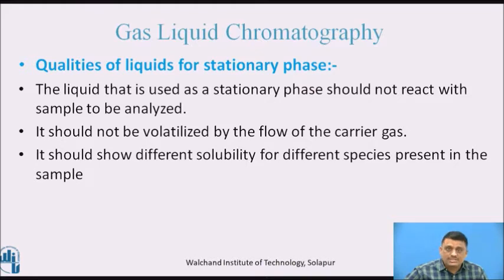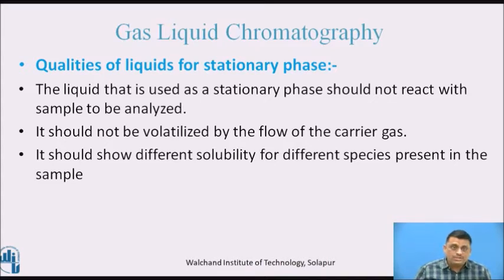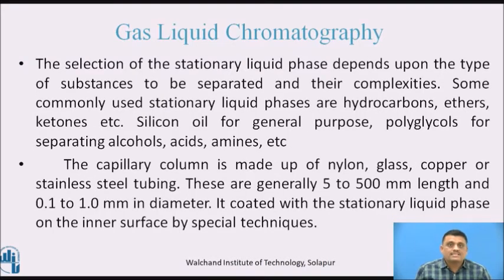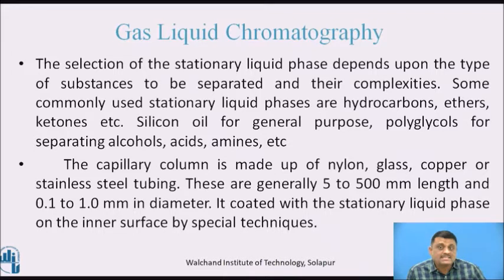Regarding the qualities of liquid for the stationary phase: the liquid used as a stationary phase should not react with the sample to be analysed — it should be inert. It should not be volatilised by the flow of the carrier gas, so the liquid should remain in liquid form and should not convert into vapours due to gas flow or heating. It should show different solubility for different species present in the sample. The selection of the stationary liquid phase depends upon the type of substances to be separated and their complexities. Commonly used stationary liquid phases include hydrocarbons, ethers, ketones, silicon oil for general purpose, and polyglycols for separating alcohols, acids, amines, etc.